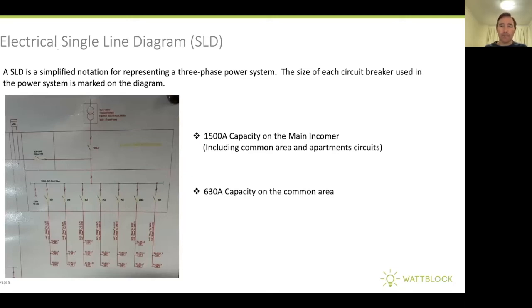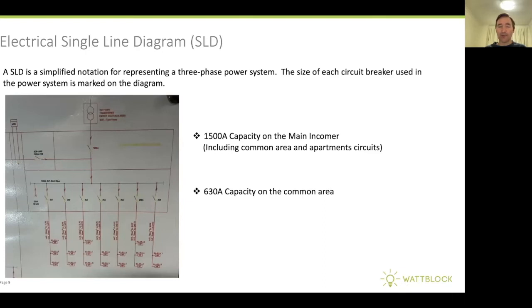What is an electrical single line diagram? Ideally, every strata building would still have the original electrical single line diagram from when the building was constructed. If it's not a relatively new building built in the last five or so years, there's a good chance this diagram has been lost, or was never created for some really old buildings built in the 60s and 70s. Single line diagrams are simplified notation for representing a three phase power system. You can follow the circuits and see what the amps are on different circuits, branching off to show common area and apartment circuits. Here's an example of a single line diagram showing 630 amps capacity on the common area.